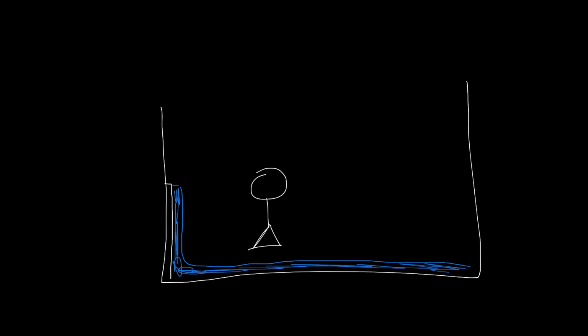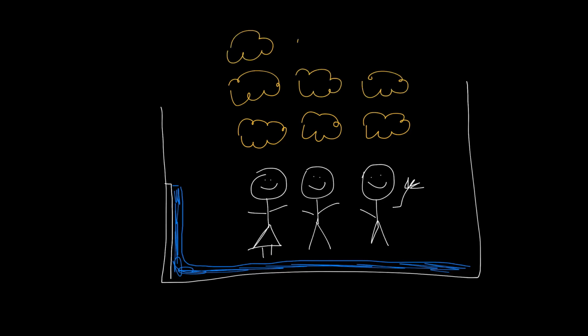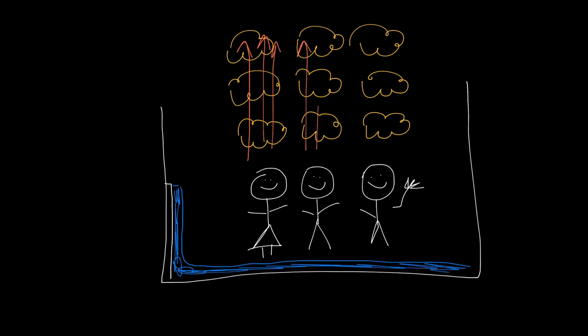When convective heat sources, for example, students in a classroom, are introduced to the space, they give off heat to the environment around them. In the absence of turbulent forces in the space, this heat forms convective heat plumes that rise along the body of the heat source and continue to grow and rise to an elevation where they either contact the ceiling or encounter equally warm air.